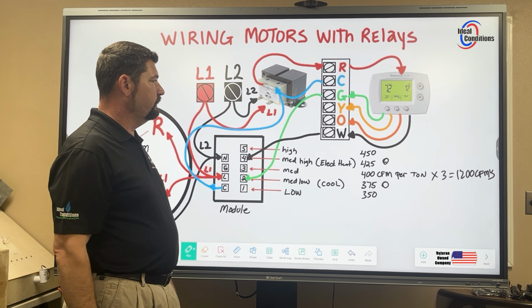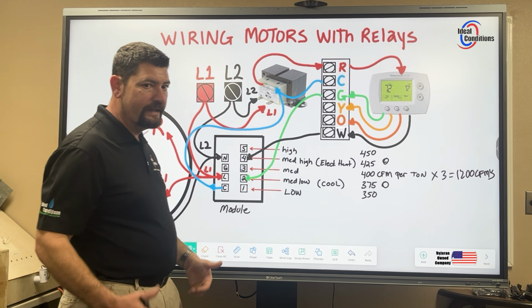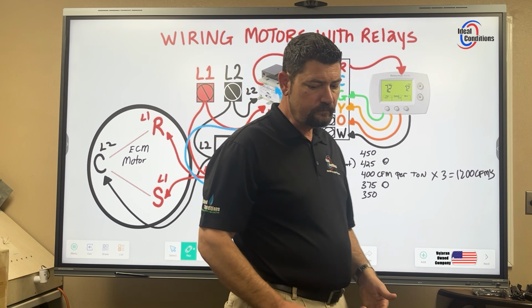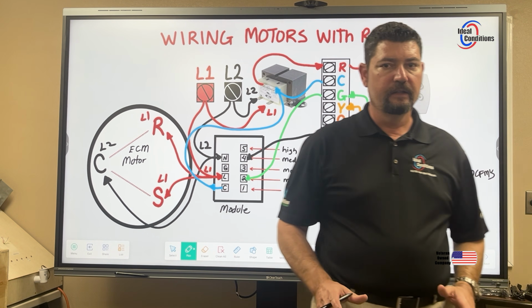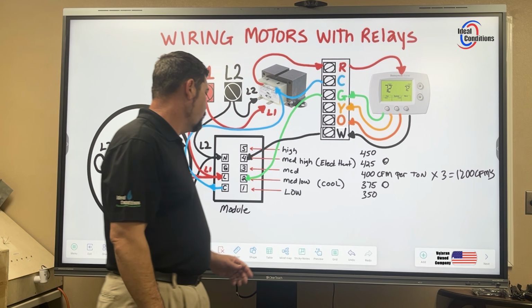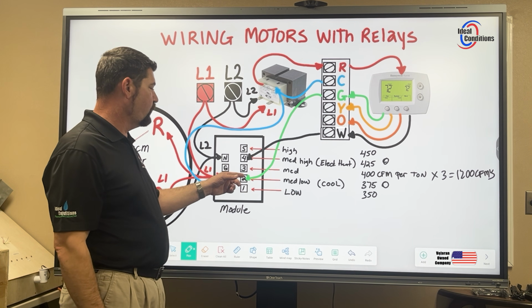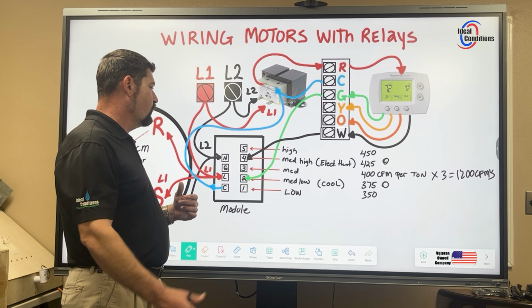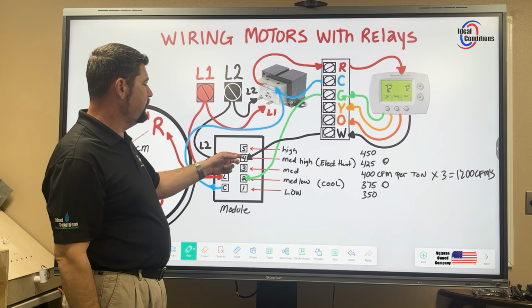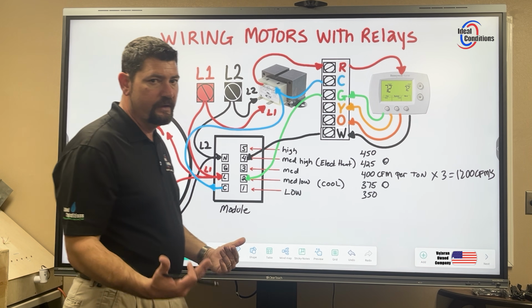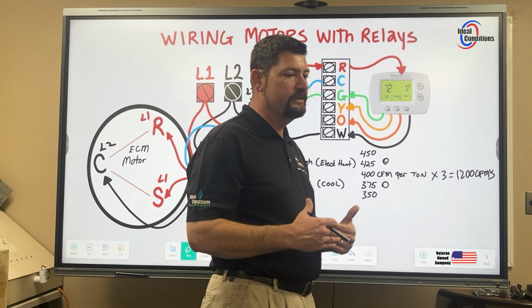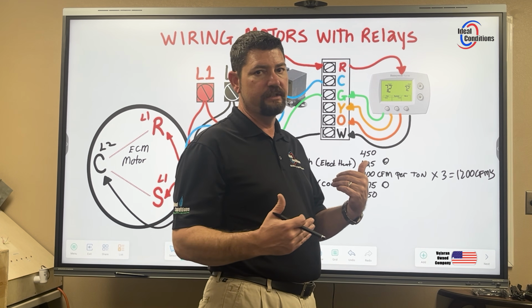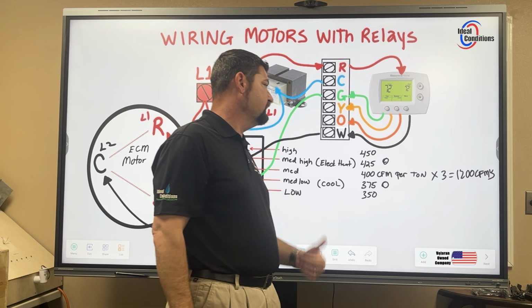medium high up. Now, let's just say I had a Y1, Y2 situation, okay, and I had no electric heat. Now I can do the same thing. I can say, okay, Y1 low speed, I'm going to wire to terminal 2, and Y2 high speed, I'm going to wire here to terminal 4. Same thing, 2 stages. If I increase my BTUs, I need to increase my CFMs with those BTUs.